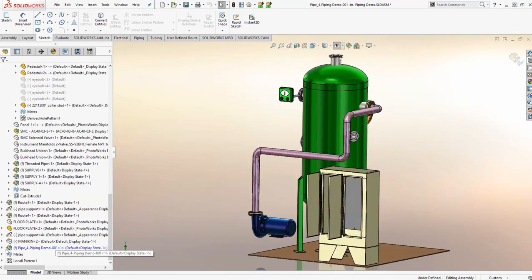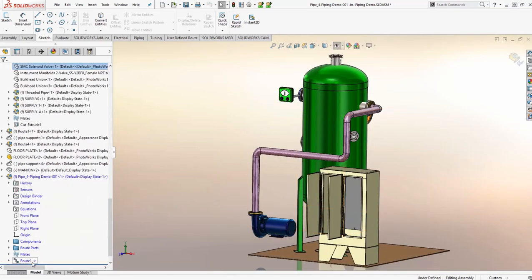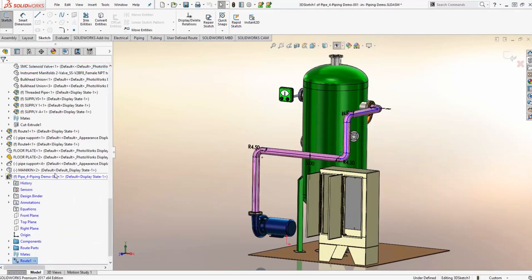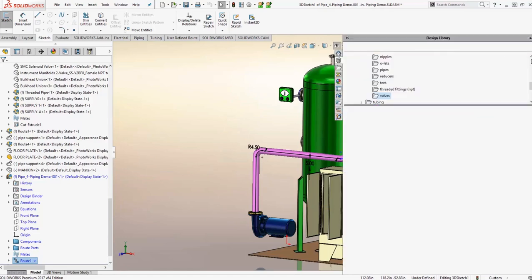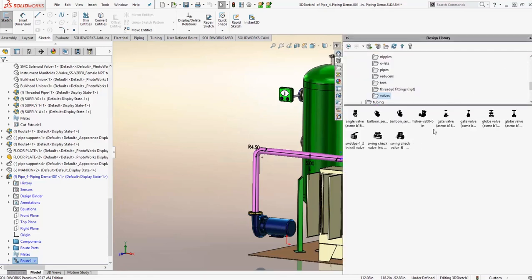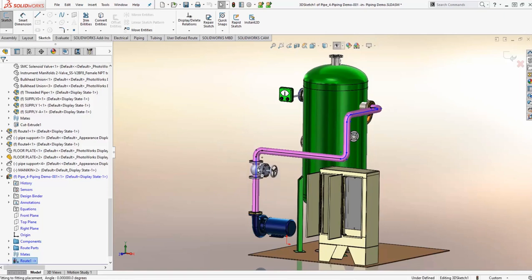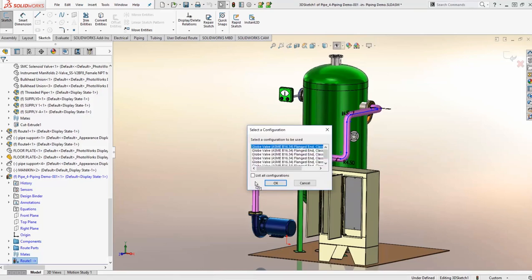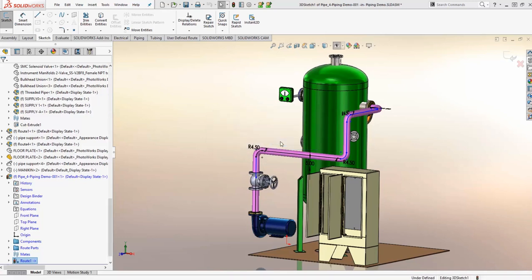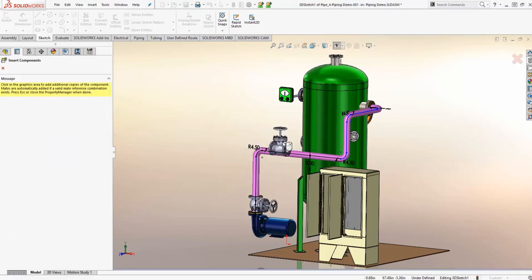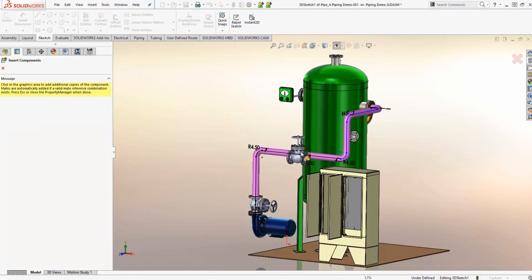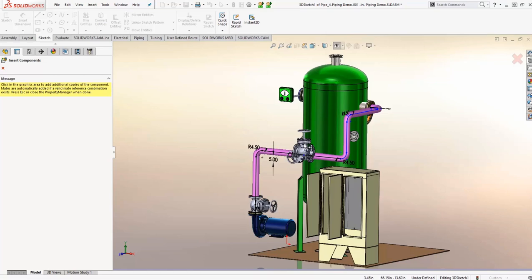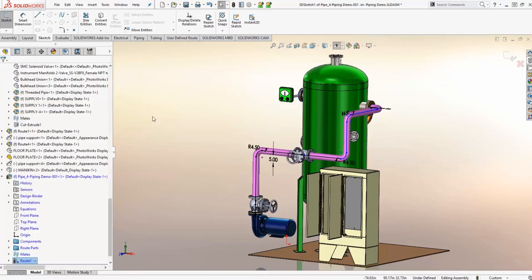Even after we completed the route, we can still go back into that and edit the route that we just created and be able to drag and drop other components onto that route. The route sketch is still active. We can now just go in and simply drag and drop some type of valve. It resizes automatically based off of the configurations and based off of the pipe size. We can then pick and choose the schedule that we want to use, the size of the pipe and the schedule. And we can even take it down and not have a length of pipe there. It can be mounted directly on top of that flange. And you can see I'm still in that process. This time I'm not going to set that up. But just dragging and dropping that in there will actually cut that pipe at those locations.